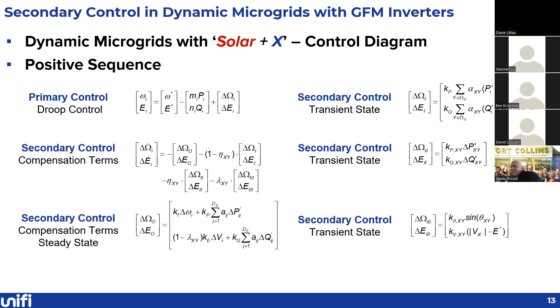That is what we developed for the positive sequence control diagram. For the negative sequence control diagram, we also considered that. The motivation is that our US distribution network is mainly an unbalanced distribution network. So focusing on incorporating dynamic microgrids into the unbalanced distribution network, we need to consider the unbalance, which can be managed using our negative sequence control.